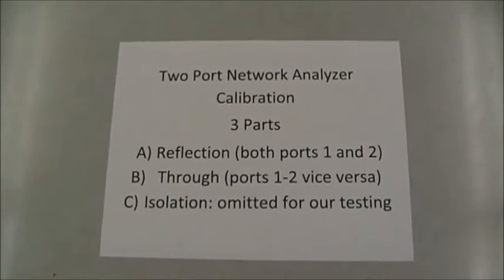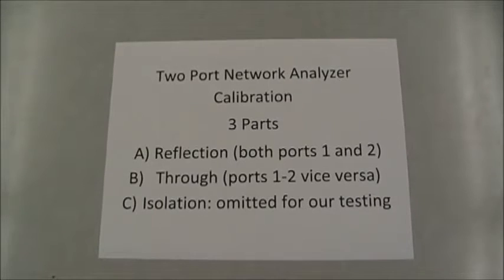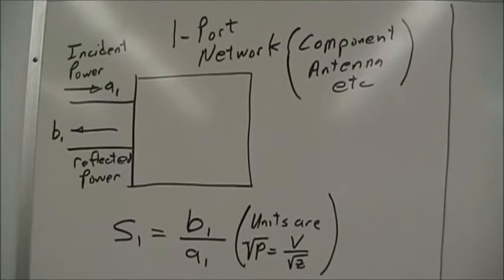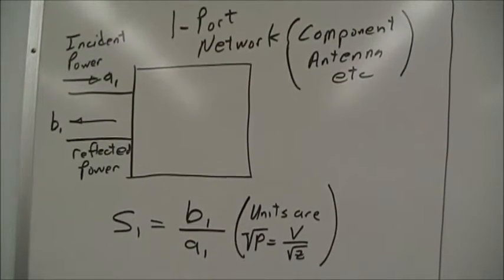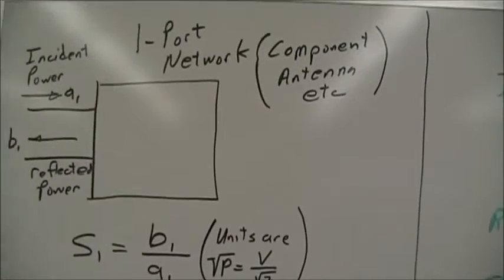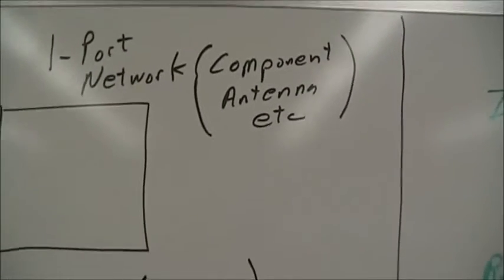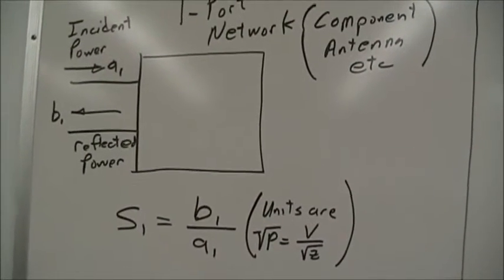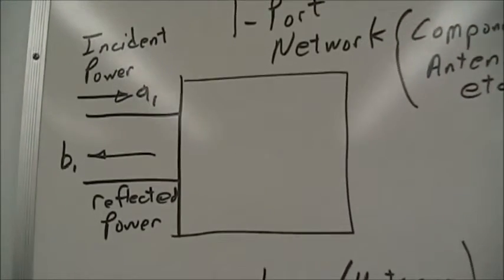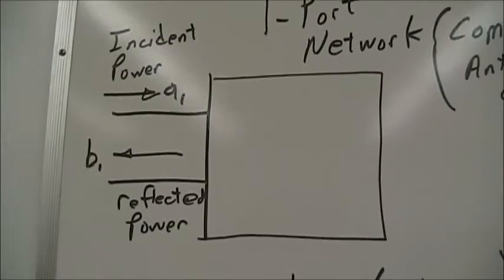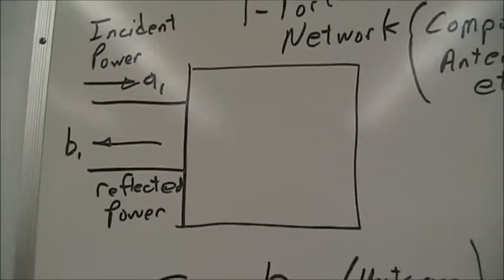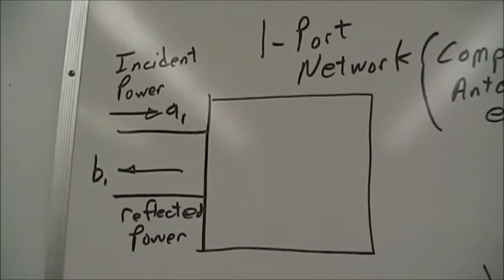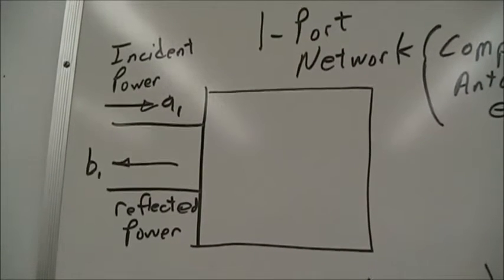As part of the beginning work for the two-port network analyzer calibration, we need to review the single port network analyzer calibration. For the last two weeks we have been doing one-port network analyzer work looking at components and antennas. A one-port network analyzer situation is where you have incident power and reflected power.